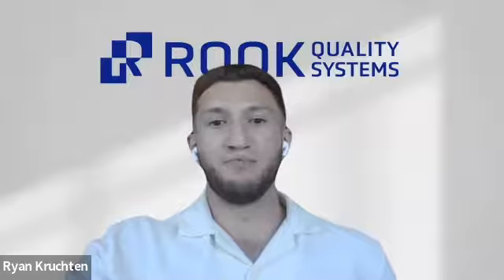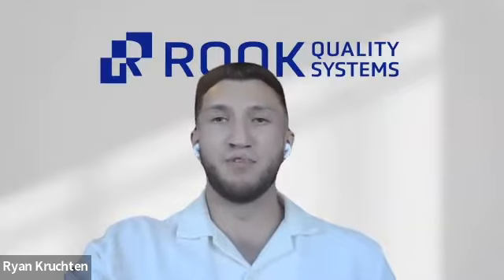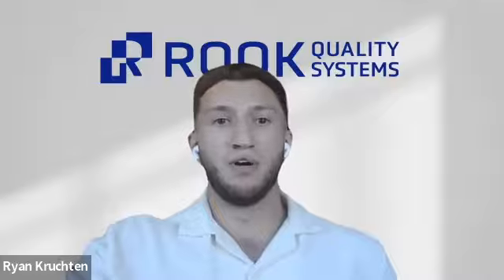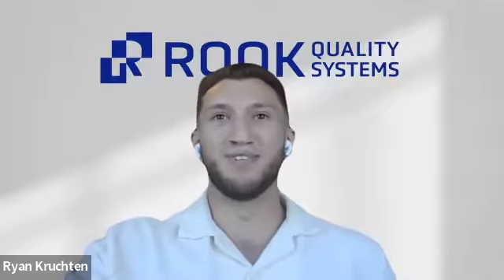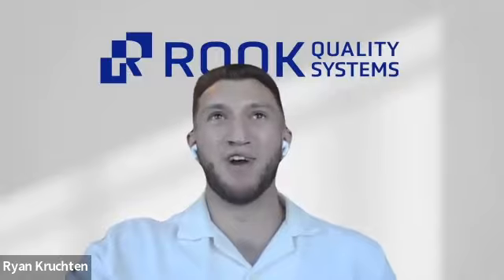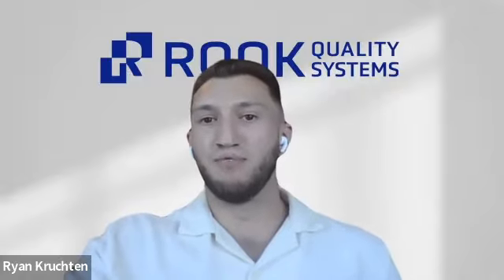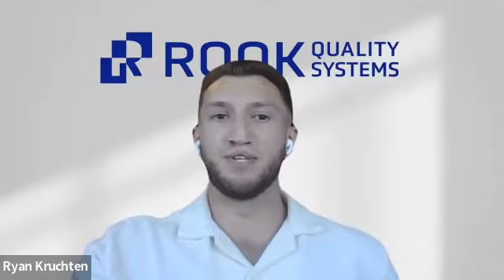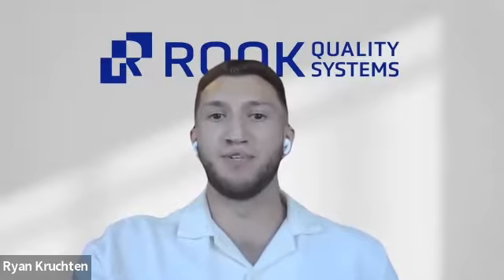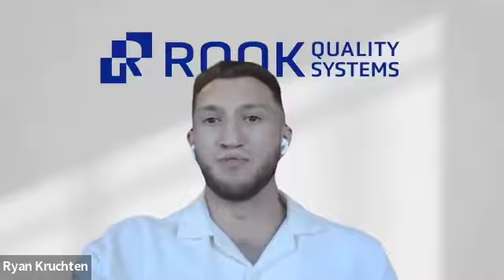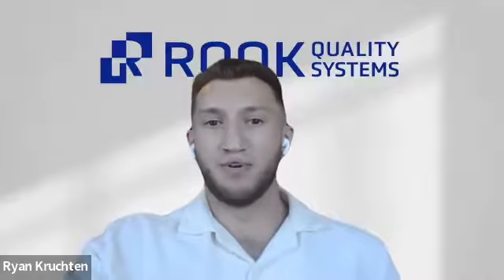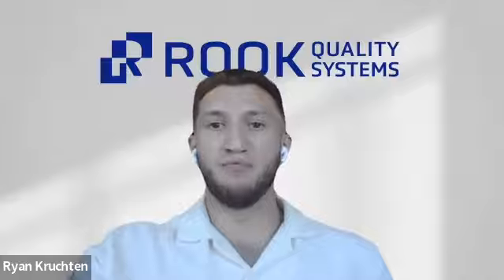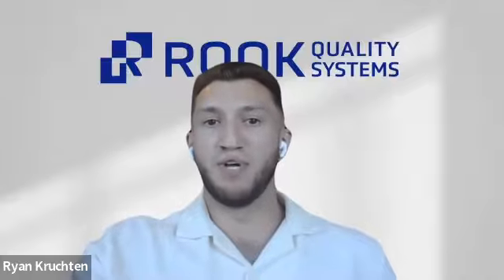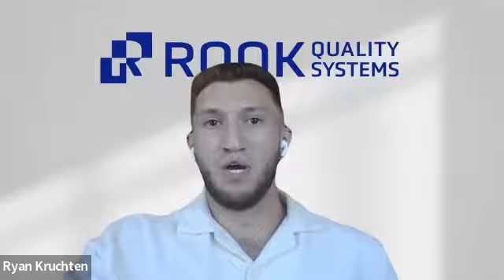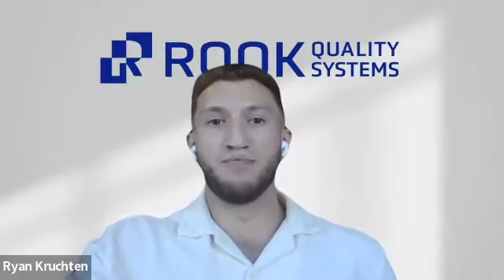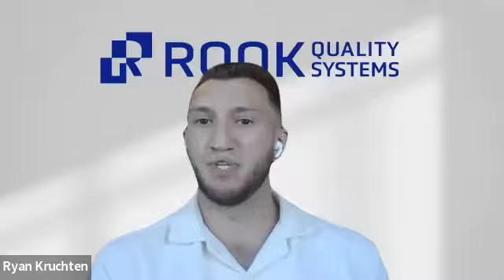Now, the first question is, how do we choose the right method between Agile and Waterfall? And like any good consultant would say, the answer is it depends. The truth is that it's not always binary. Waterfall tends to work well when requirements are fixed. So things like supporting software in a device, such as an embedded firmware with minimal user interaction. Agile, on the other hand, supports iterative development and is ideal when requirements evolve, such as with mobile apps or AI-driven diagnostics.